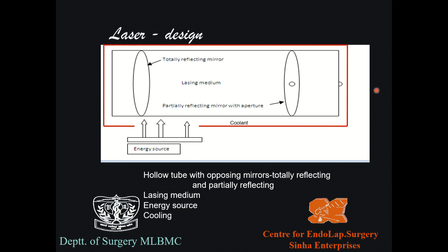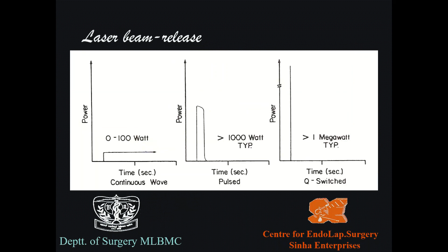The whole device is a chamber with atoms reflecting between two mirrors — one totally reflecting, one partially reflecting — because the energy source has pushed them to a high energy state. When the energy source stops, atoms release energy channeled through a small aperture for a variable time period, delivering photons onto the application site. A coolant passes through an outer sheath to keep the inner tube cool, since very high temperatures are generated.